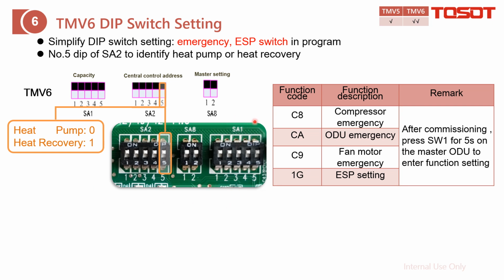SA1 is for the capacity. Please keep it unchanged. SA8 is for setting it as the master or slave. As for the SA2, the 4 dip is for the centralized address. As for the last one, the number 5 dip is to identify whether it is the heat pump or heat recovery system.